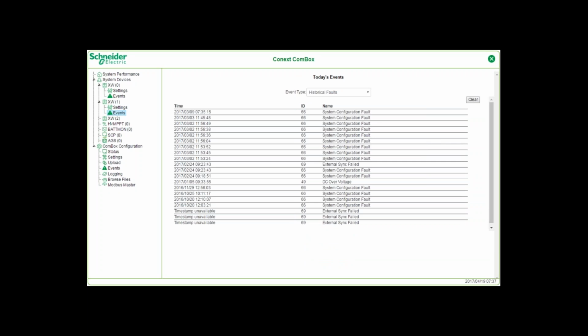The events list real-time and historical faults and warnings for each device. So we can see here that we've got some system configuration faults. This is the system in Costa Mesa. This is our test lab. Many times it's necessary to disconnect a particular inverter, reduce the triple inverter size maybe down to a single unit to simulate a particular scenario for a customer. So here we can see that over a particular range of time there were some system configuration faults, DC over voltage or certain things. But anyway, this is a great source so you can go back and see what's been going on with the XW or any device that's in the network for that matter.